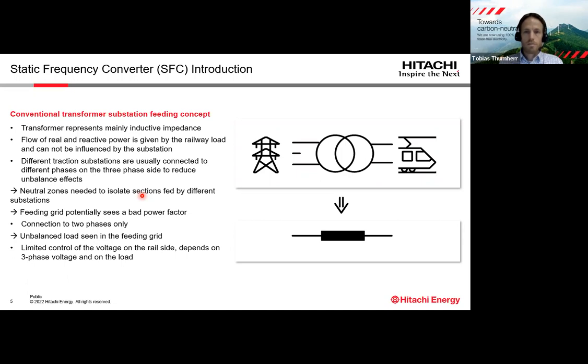This means also that the feeding grid potentially sees a bad power factor. The power factor is basically given by the load and cannot be influenced, or it could maybe by adding additional components. Then the transformer substation is connected to 2 phases only, because the railway system is a single phase system. And this means that there is an unbalanced load towards the 3-phase feeding grid. And this unbalanced load will result in a voltage unbalance.